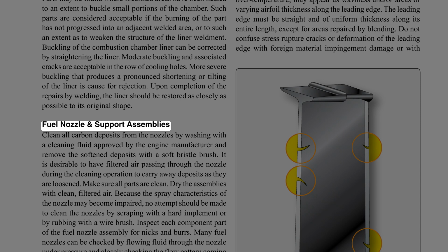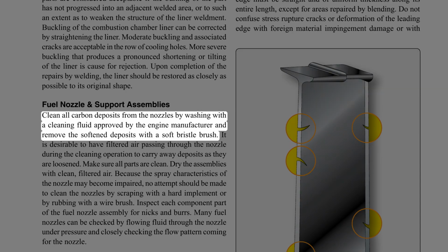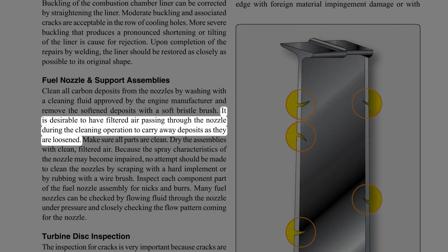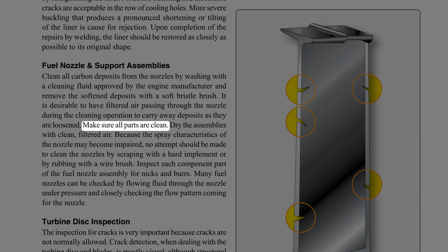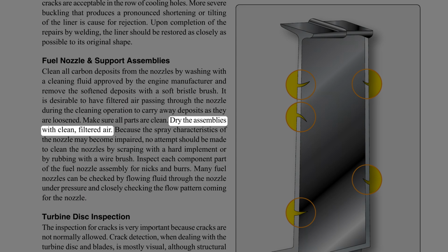Fuel nozzle and support assemblies. Clean all carbon deposits from the nozzles by washing with a cleaning fluid approved by the engine manufacturer and remove the softened deposits with a soft bristle brush. It is desirable to have filtered air passing through the nozzle during the cleaning operation to carry away deposits as they are loosened. Make sure all parts are clean. Dry the assemblies with clean, filtered air.